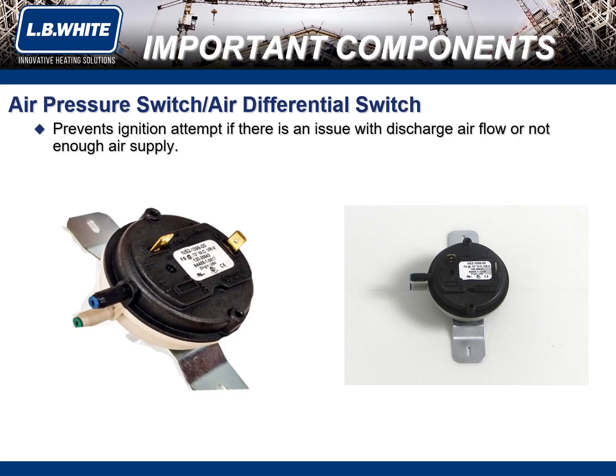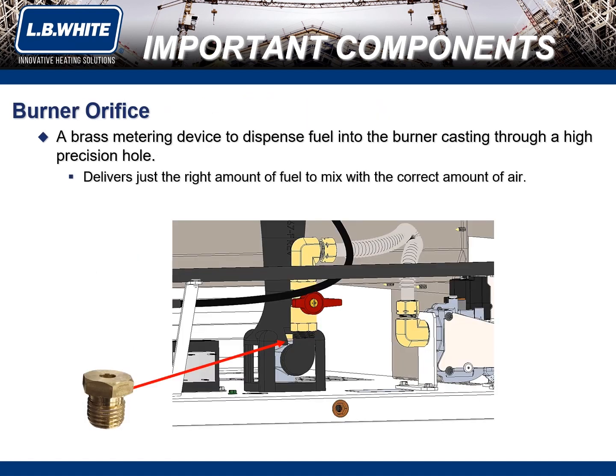As an example, if a piece of paper flew up and got stuck to the air intake end of a heater, the heater would stop receiving the proper amount of air intake and the air pressure switch would be triggered. A burner orifice is a brass metering device that dispenses fuel into the burner casting through a high-precision hole. It delivers just the right amount of fuel to mix with the correct amount of air.